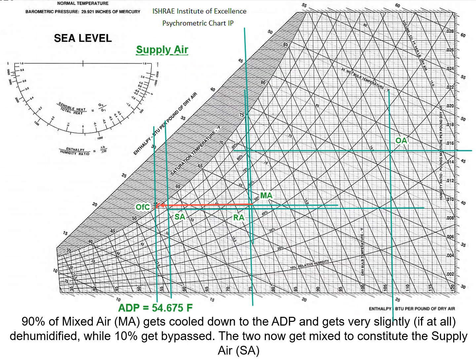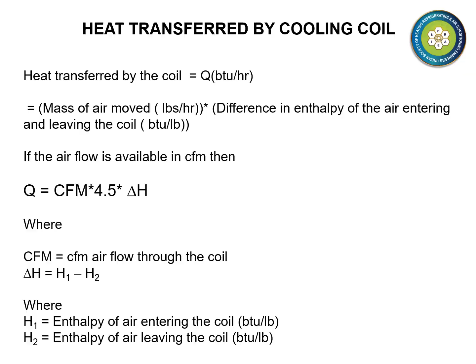In this slide, we show how to calculate the heat removed by the cooling coil, knowing the unbypassed airflow through the coil and the on-coil and off-coil enthalpies of the air. In this slide, we show how to pick off the on-coil and off-coil enthalpies from the psychrometric chart and thereafter estimate the heat removed by the cooling coil. We are able to estimate the heat removed by the cooling coil to be 366,947 BTUs per hour.